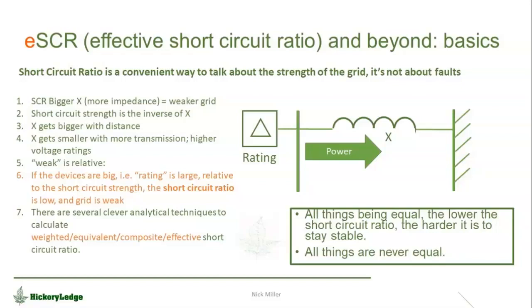So short circuit ratio is a very convenient way to talk about how strong the grid is, and I've made as simple a cartoon grid as I can possibly make in the drawing here. Got my converter-based device on the left, stuffing power into a grid that's characterized by its impedance X. Can't make it simpler than that.